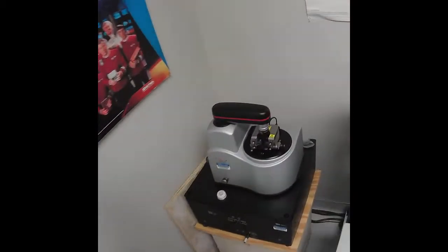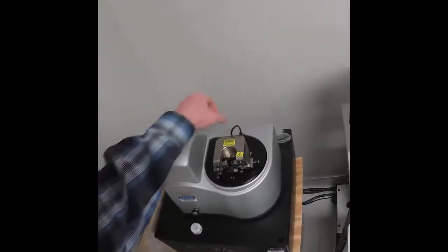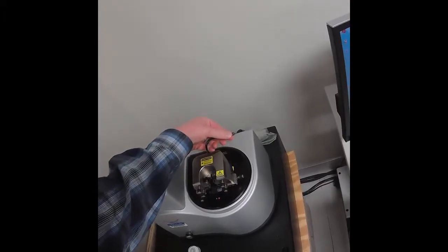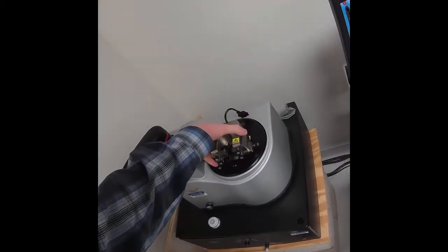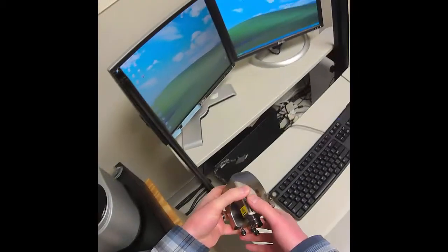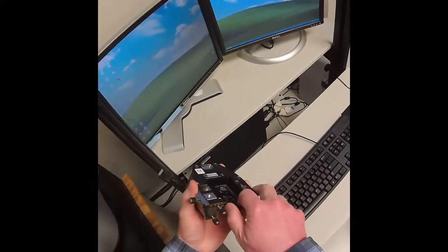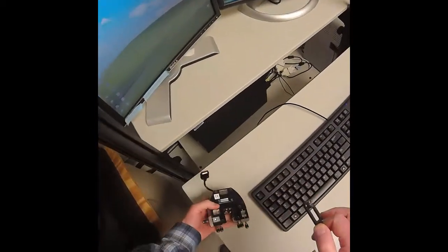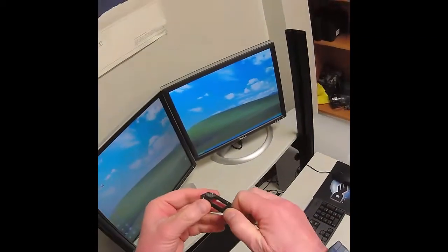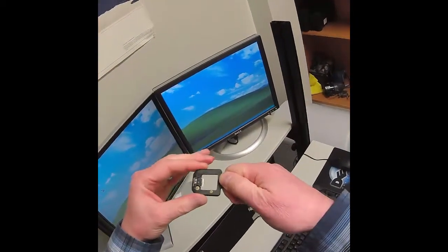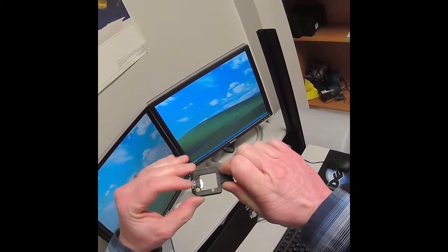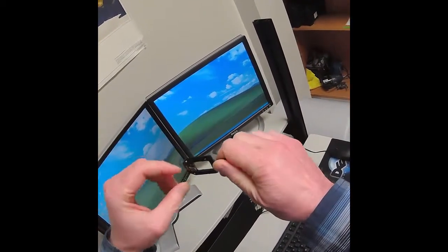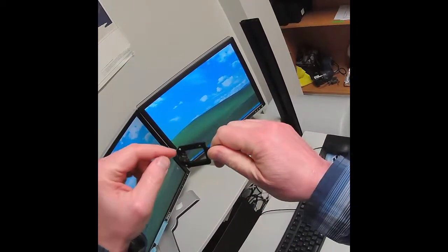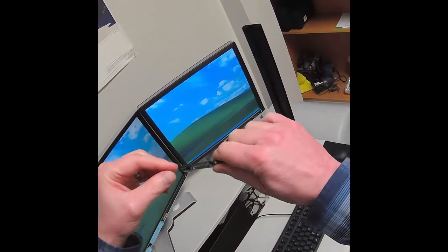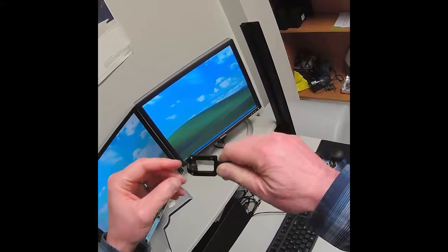Let's prepare the sample to use in phase mode. So we squeeze the pin here to release the plug and gently lift up the scanner head, and we can check that we have the right cartridge in the scanner head for tapping mode. When we want to look at phase, we need the tapping mode cartridge, and we can see that it's tapping mode because we can see there's these leads here, and there's a little tan chip inside that's a little piezoelectric crystal that will vibrate the tip.